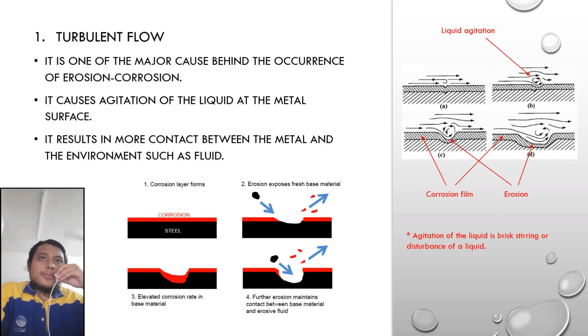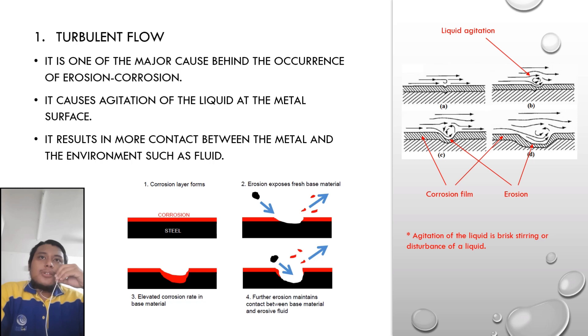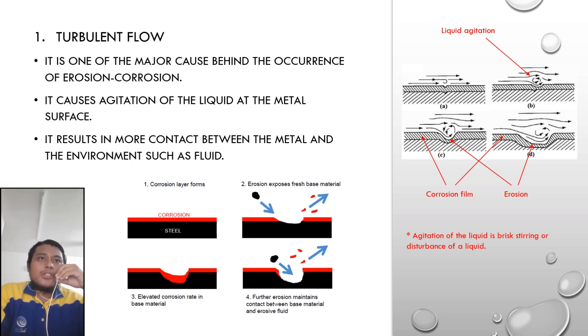For turbulent flow, it is considered one of the major causes behind erosion corrosion. For example, in a water pipe, liquid flow such as water will create a corrosion layer onto the metal. Then particles inside the water will scrape the corrosion layer, creating small holes that cause agitation of the liquid at the metal surface. The liquid agitation results in more scraping of the layer, creating more contact between the metal and the environment, which is water.